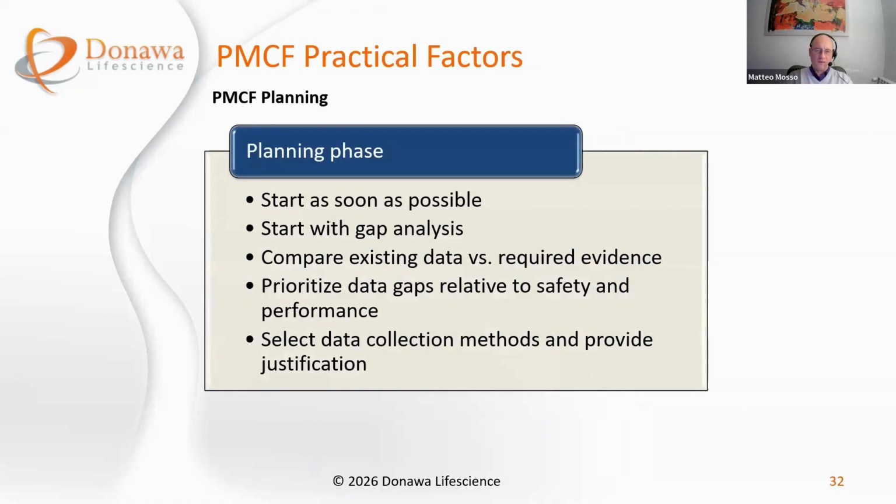So, what are the key considerations for planning PMCF data collection? The advice is to start as soon as possible and to start by performing a gap analysis in order to compare the existing data against the required evidence that you need.